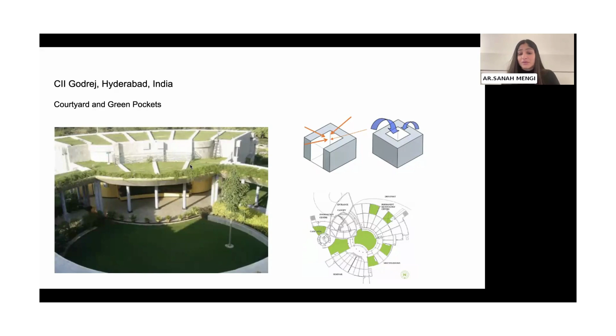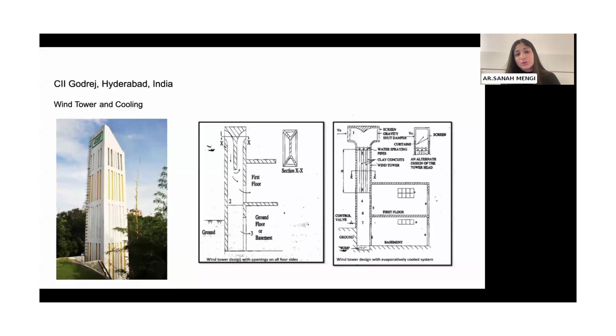The wind tower and cooling tower, in this case unlike the previous example, takes cold air from the wind tower down to the basement of the building, where there is an air handling unit and chiller system. All the cold air goes to the AC system, reducing the pressure required at the inlet. The supply air is already cold, so it reduces the load on the HVAC machinery to cool the air and send it back into the building. That has reduced a lot of energy requirements, and it's used for only a few months anyway.